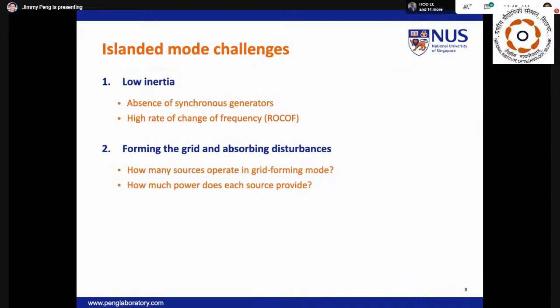Different to a utility grid, a microgrid will most likely have a significantly smaller net inertia due to the absence of large synchronous generators. We can imagine inertia as a buffer that helps to buy operators time to react to transient events within a power grid. Now, a low inertia system will exhibit a relatively faster transient response in the context of frequency variation, which can trigger protection relays if dynamics are not properly mitigated.